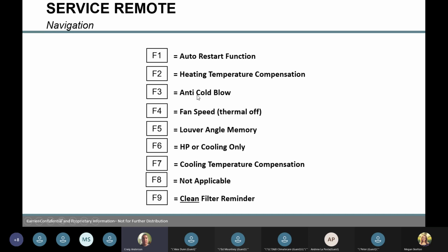Anti-cold blow. So the unit's going to heat up before the fan turns on. We can turn that on. We can turn that off. If you have a heat pump unit and they only want cooling, you can turn the mode off. You can turn the heat pump mode off, or you can turn the cooling mode off and just have heat pump if that's a function they want.